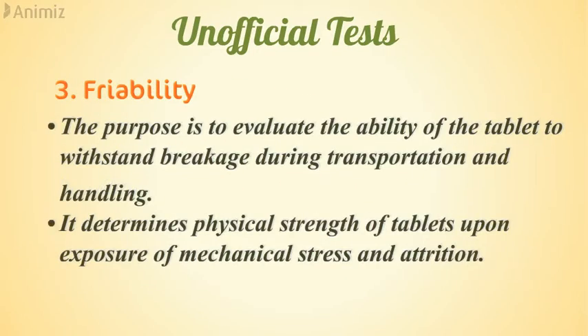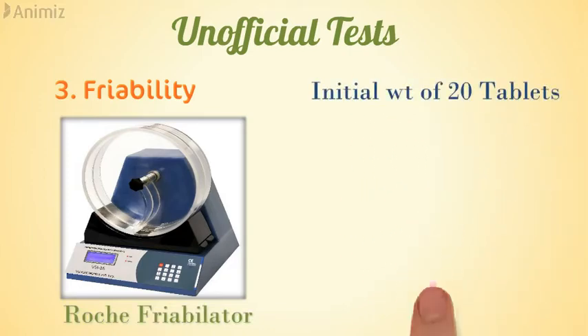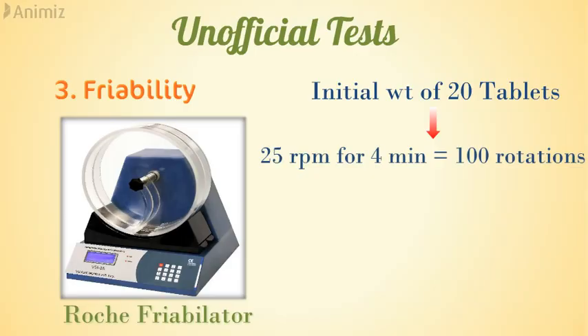The third test is friability. Its purpose is to evaluate the ability of a tablet to withstand breakage during transportation and handling, determining physical strength upon exposure to mechanical stress and attrition. Friability is measured using a Roche friabilator: the initial weight of 20 tablets is measured, and they are rotated for 4 minutes at 25 RPM.